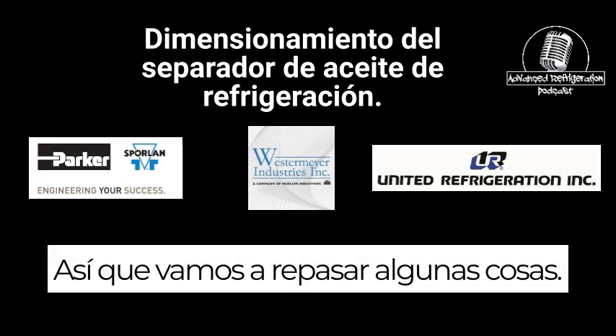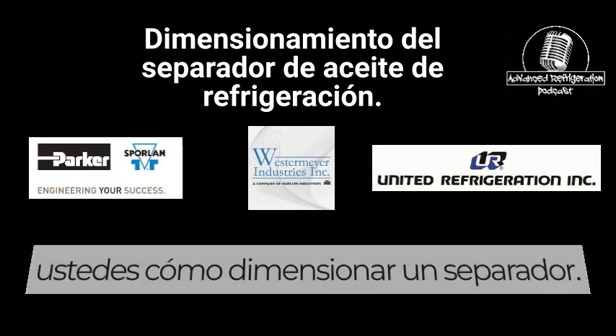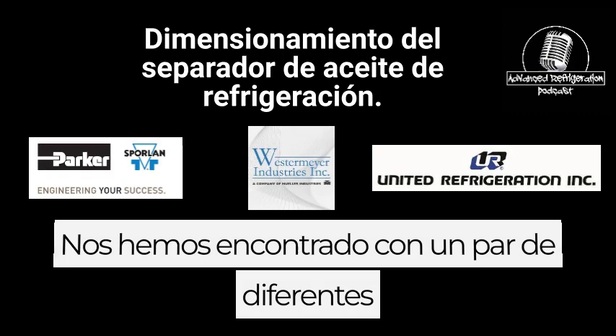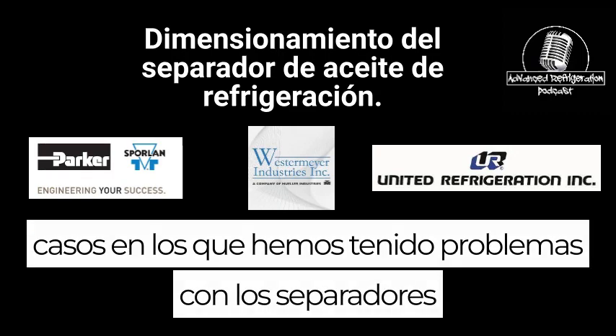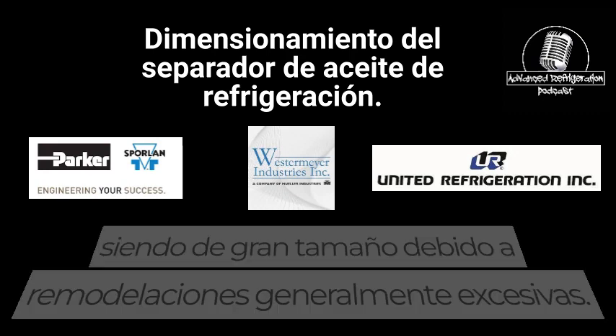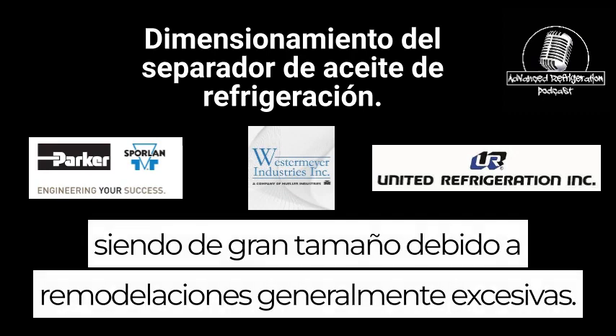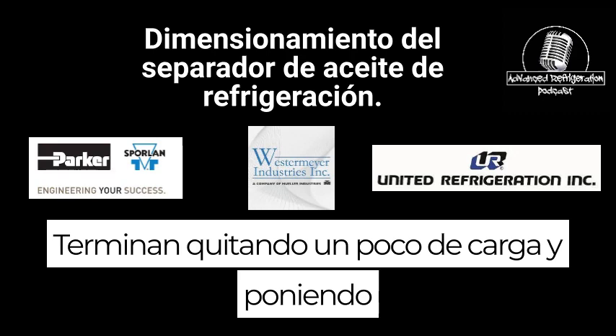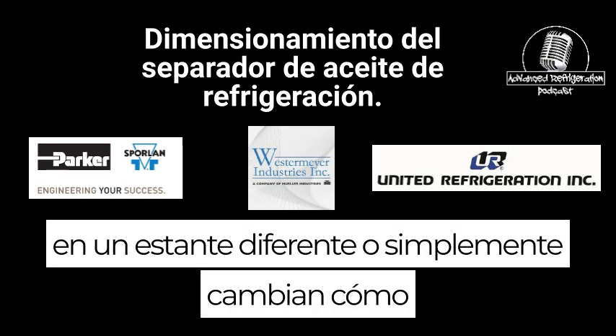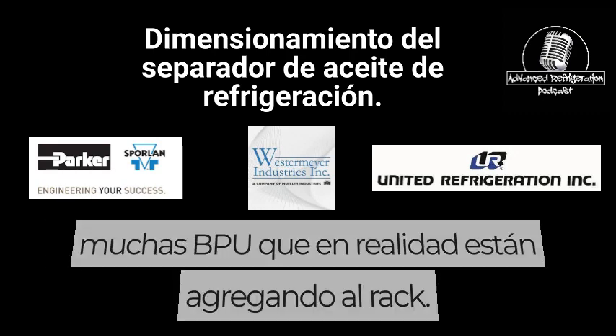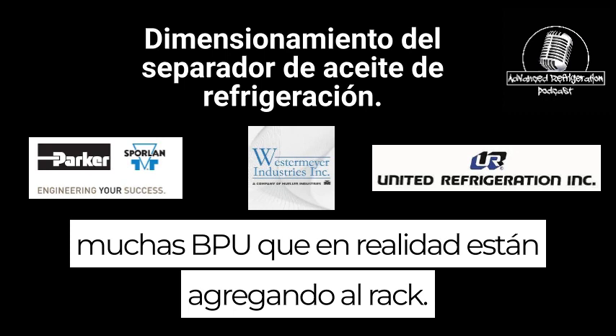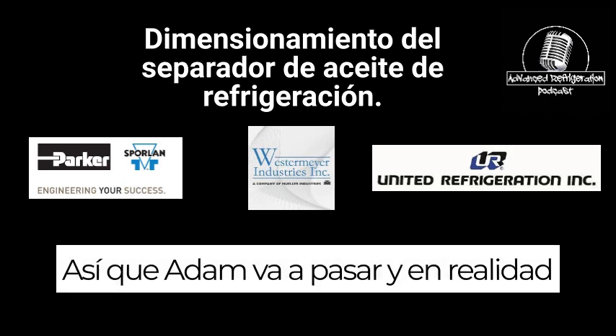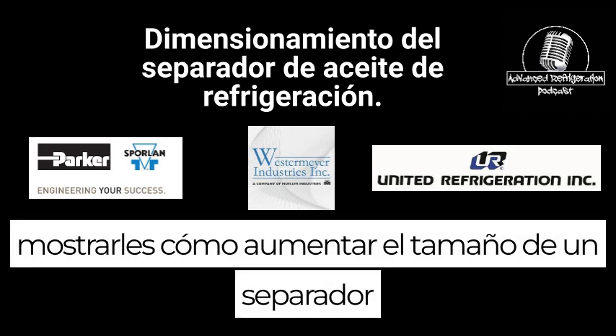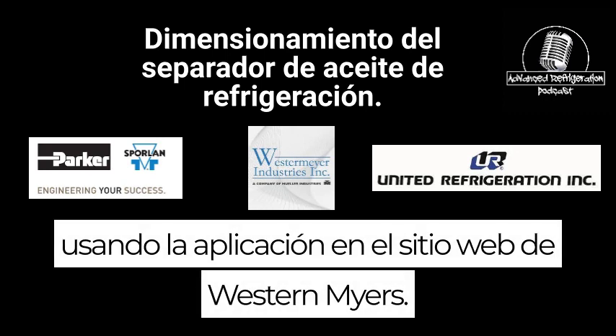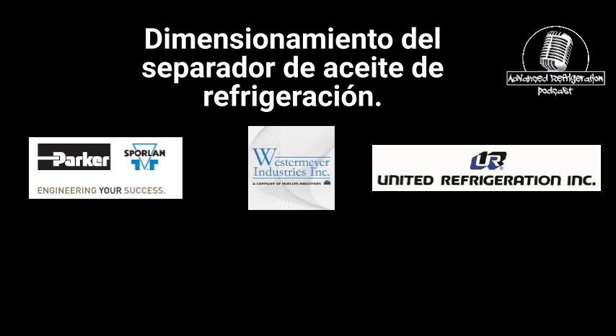So we're going to go over some things. First things first, we're going to show you guys how to size a separator. We've come across a couple different instances where we've had issues with separators being oversized, usually due to remodels. They end up taking some load off and putting it on a different rack, or they just change how many BTUs they're actually adding onto the rack. So Adam's going to go through and actually show you guys how to size a separator using the application on Westermeyer's website.